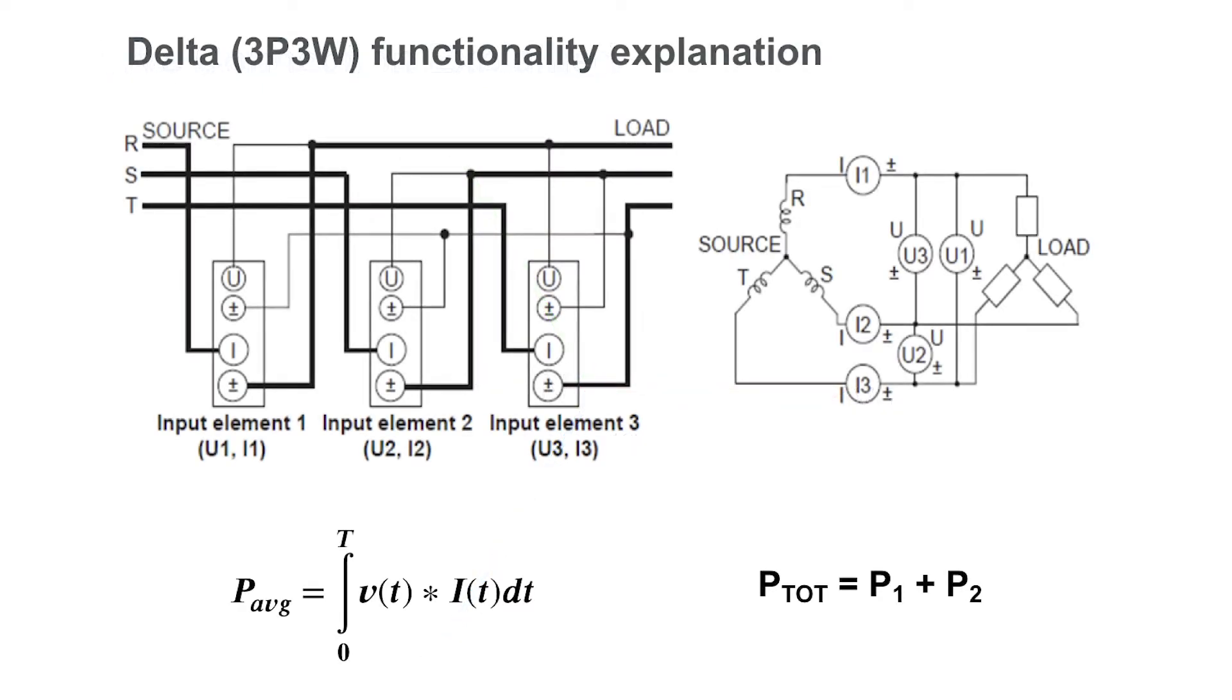However, more often than not in motor testing, we do not have a neutral available to reference. In these cases, we have to wire our voltage in a delta connection that will reference the voltage of each phase to another phase. As you can see when wired in this method, we get line-to-line voltage rather than line-to-neutral voltage.